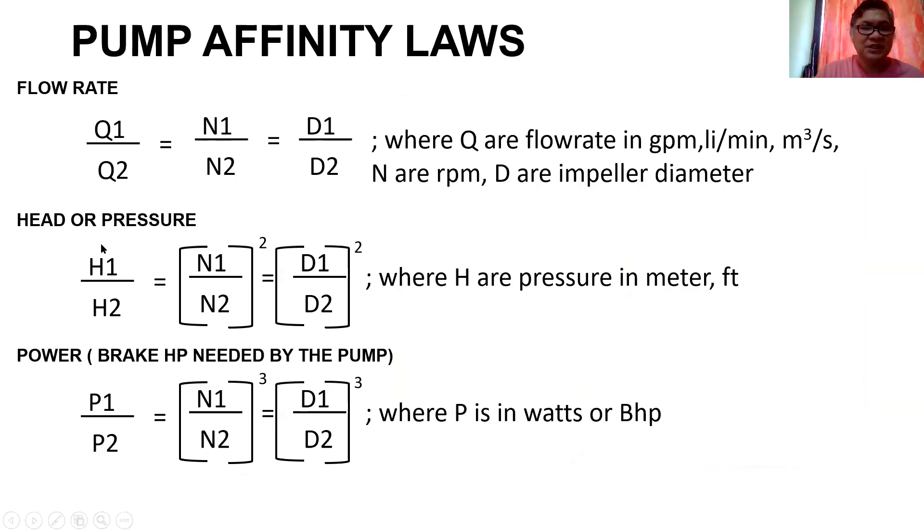The head or the pressure H1 over H2 is equivalent to the square of the speed N1 over N2 squared and D1 over D2 squared. The power P1 over P2 is equivalent to the cube of the speed N1 over N2 cubed and D1 over D2 cubed.